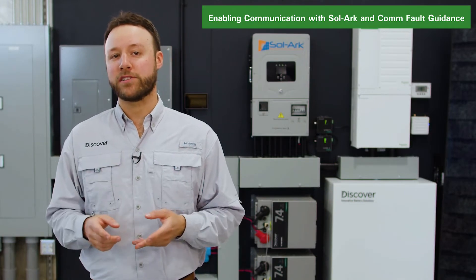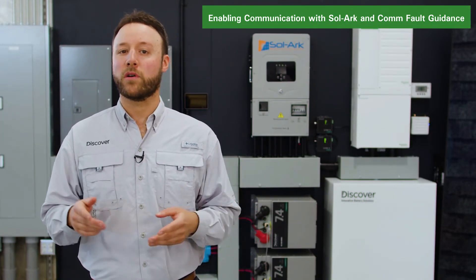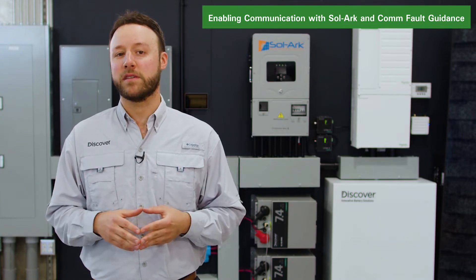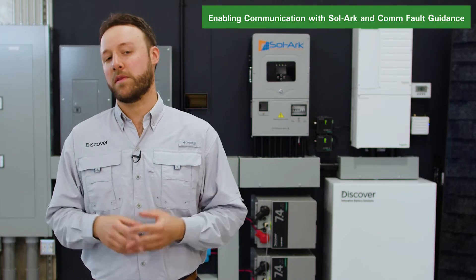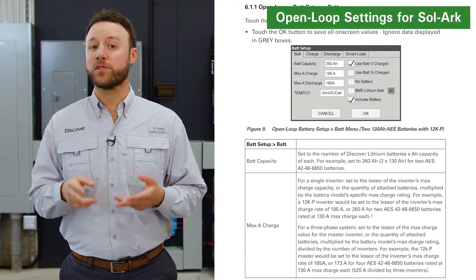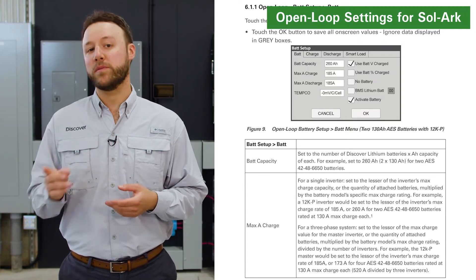As a precautionary measure, we recommend first programming the Sol-Ark inverter with the correct voltage-based open-loop parameters before setting up the system to function in a closed-loop configuration. Referring to section 6.1 of the LYNK II Sol-Ark user manual, you will find the list of Sol-Ark open-loop settings.